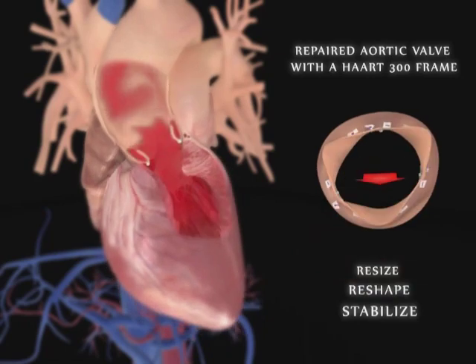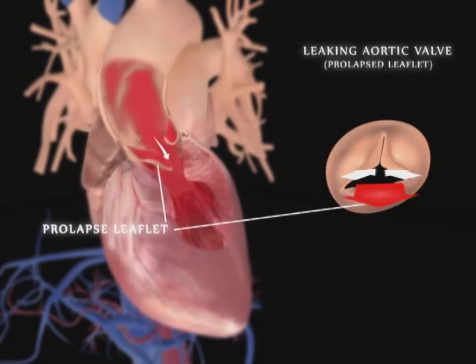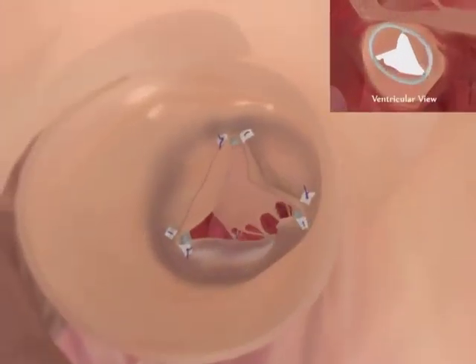Through the resizing, reshaping, and stabilization of the aortic annulus with the HAART 300 device, the aortic valve once again functions normally and does not leak. For aortic valves with prolapsed leaflets, additional sutures are used to repair the prolapse once the HAART 300 ring is implanted.